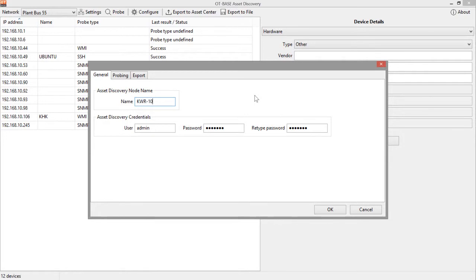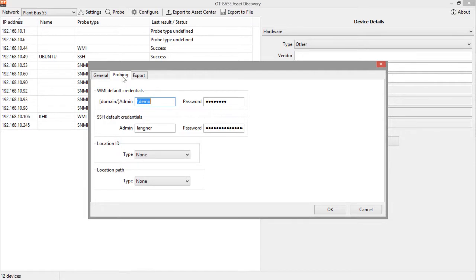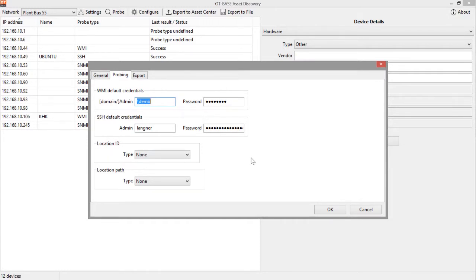Theoretically the node name could be the name of a specific network, but just keep in mind that OT-BASE asset discovery does support multiple networks. So in case your node is connected to multiple networks, obviously it wouldn't make sense to use the name of one network as the name of the node, especially considering that the node name is used as a prefix for generating device identifiers when importing configuration data into the OT-BASE asset center. Next is the probing tab in this configuration dialog where you can specify how asset discovery has identified location information in the destination RTUs, PLCs, etc. Now here's the thing.